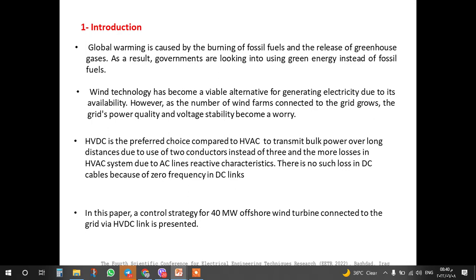High voltage DC is the preferred choice compared to high voltage AC to transmit bulk power over long distances. Due to the use of two conductors instead of three, there are more losses in a high voltage AC system, due to AC lines' reactive characteristics. There is no such loss in DC cables because of zero frequency in DC links. In this paper, a control strategy for a 40 megawatt offshore wind turbine connected to the grid via a high voltage DC link is presented.